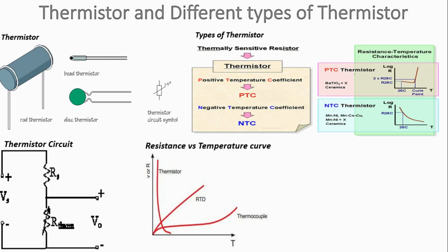Some materials provide better stability while others have higher resistances, so they can be fabricated into larger or smaller thermistors. Many manufacturers list a beta (B) constant between two temperatures. This, along with the resistance at 25 degrees Celsius, can be used to identify a specific thermistor curve.